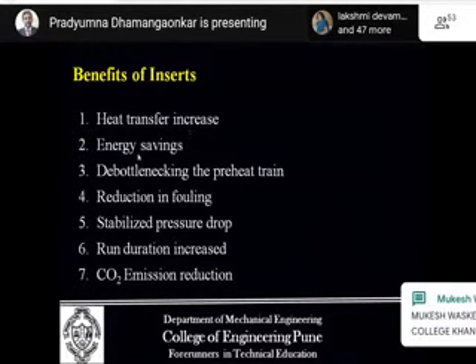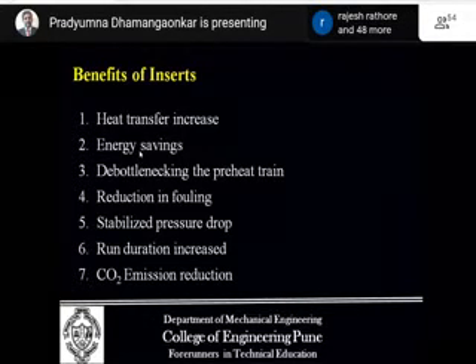Some of the benefits of inserts: first is the heat transfer increase, second is energy saving, because if there is no fouling and less pressure drop, the pumping power required is less. Without fouling, the heat transfer rate is increased, thus the efficiency is increased, and hence there is always energy saving.